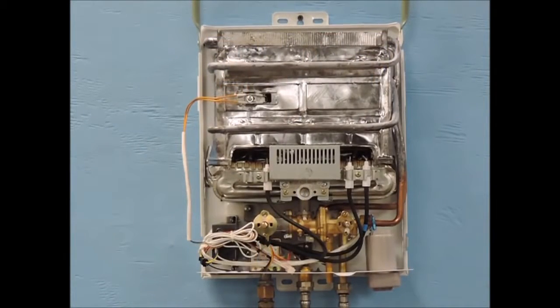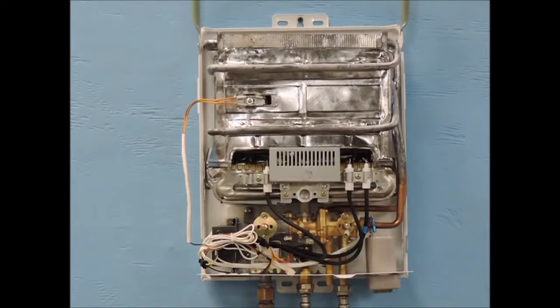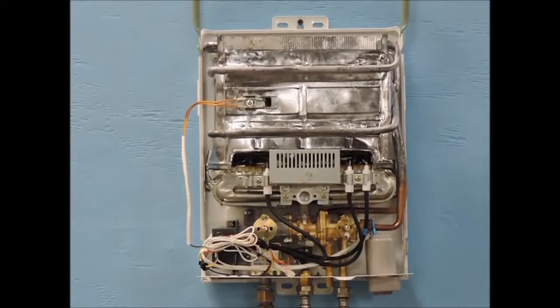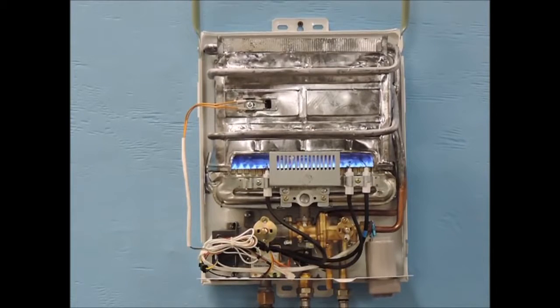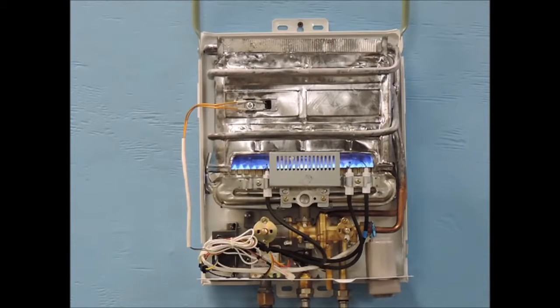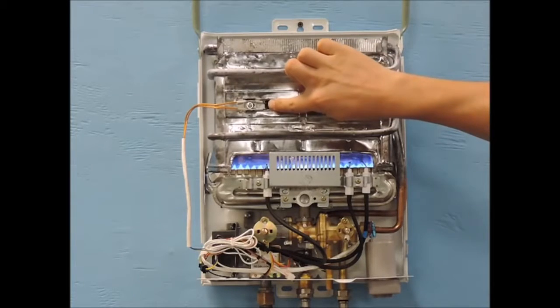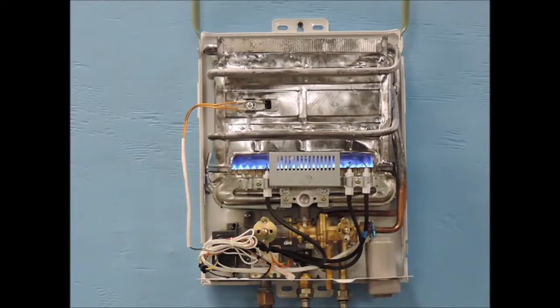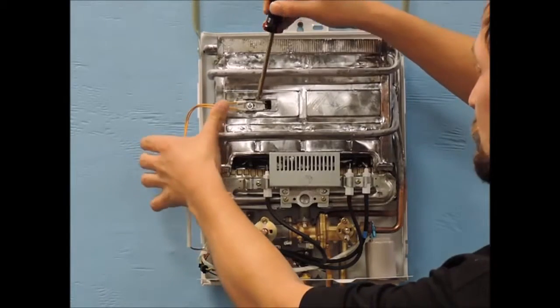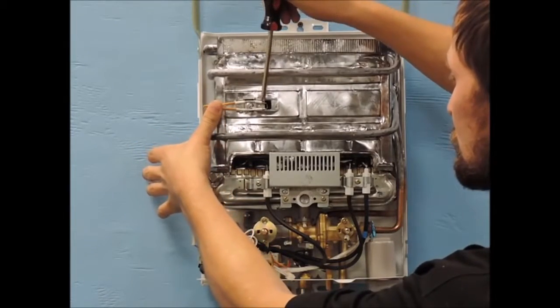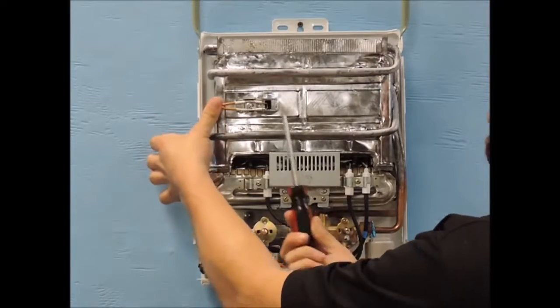If you have a Marey 5-liter portable unit, there is another sensor that could be causing the unit to light and then shut down shortly after, usually about 30 to 45 seconds. This sensor is the oxygen deprivation sensor, seen here. This sensor is mounted to the front of the heat exchanger and has two orange wires running from it. Sometimes in manufacturing or shipping, this sensor gets pushed in too far. It needs to be adjusted by pulling the sensor out with a screwdriver or pliers to where it is about a quarter to a half inch above the hole that it is mounted over.